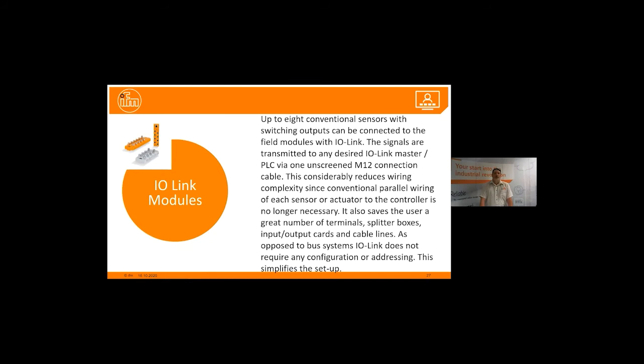Up to 8 conventional sensors with switching output can be connected to the field module with IO-Link. The signals are transmitted to any desired IO-Link master, PLC via one unscreened M12 connection cables. In other words, standard wiring is used, the same as what you are using currently. This considerably reduces wiring complexity since conventional parallel wiring of each sensor or actuator to the controller is no longer necessary. Same as with the ASI, different platform though.